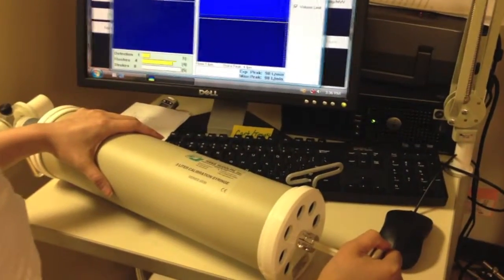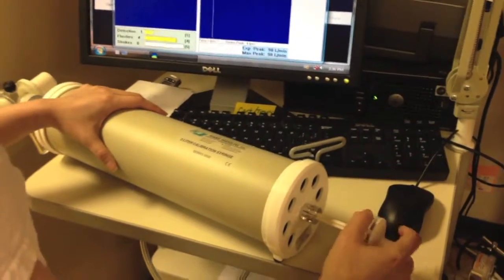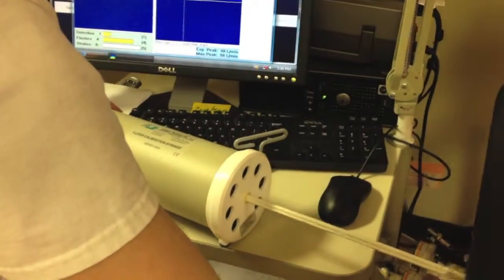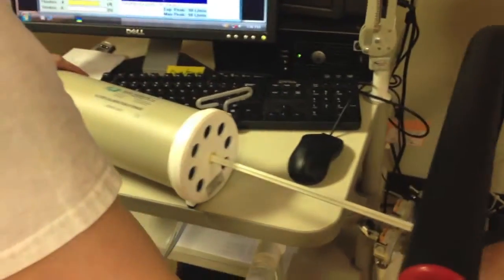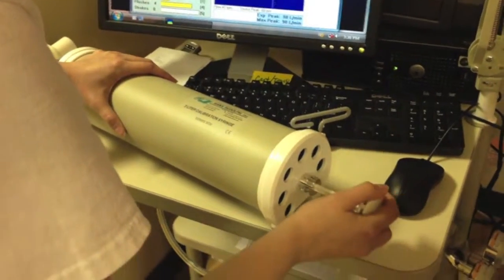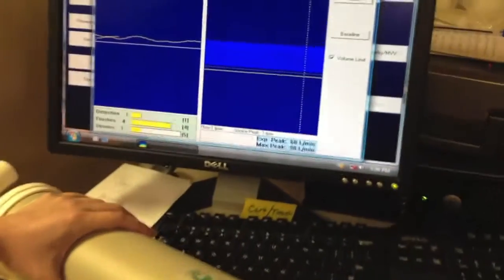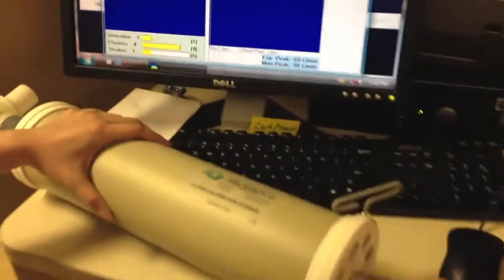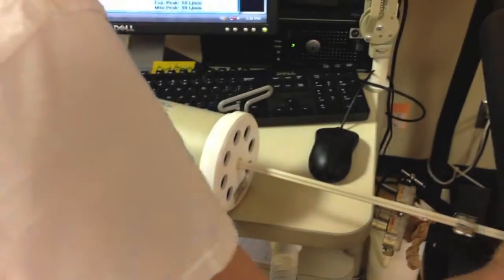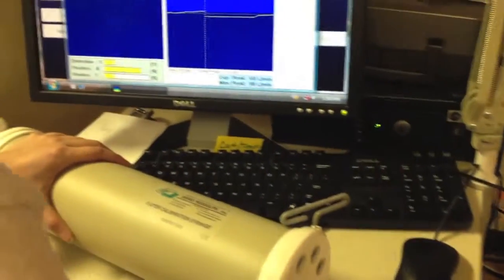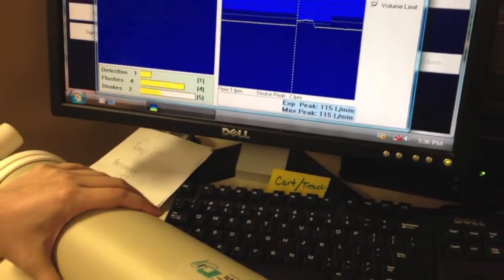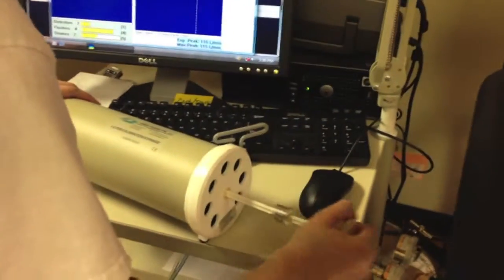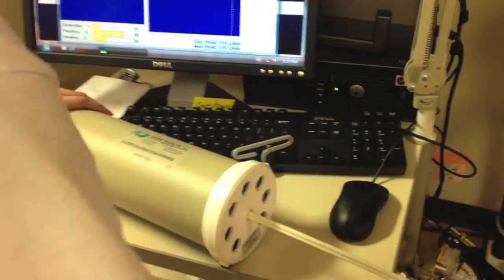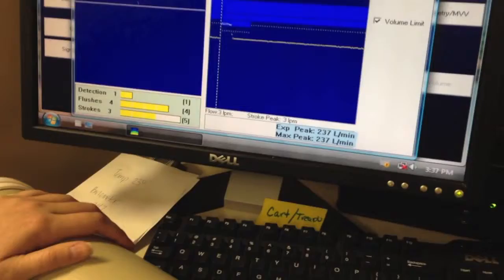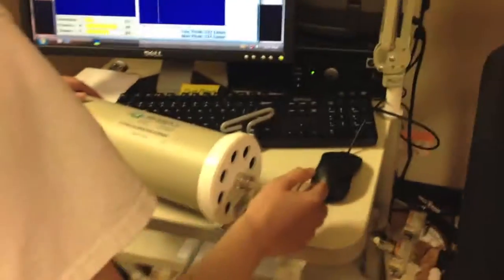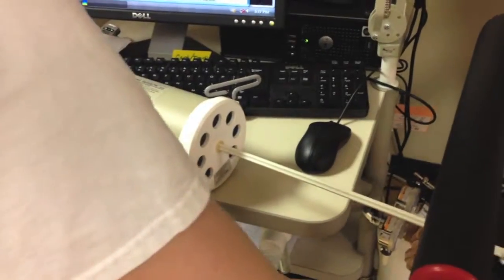Upon completion of the detection and flushes, we're going to start with our first full stroke. The next 5 strokes, you will have to pull the plunger and push back in at various speeds. There are predetermined numbers that you must hit for each stroke. The first stroke is between 50 and 80, as shown. The second stroke is between 100 and 200 liters per minute, as shown. The third stroke is between 200 and 300, as you can see there. The fourth stroke is between 300 and 400.